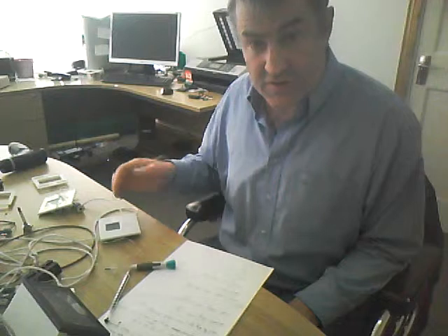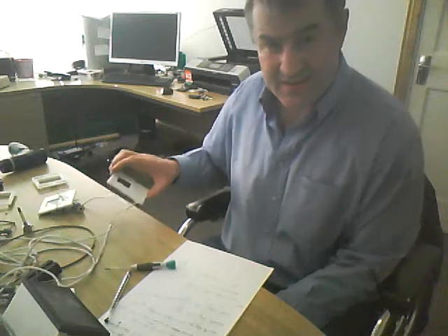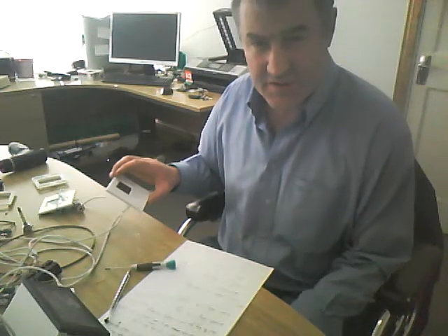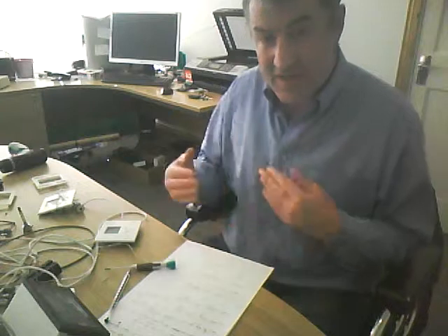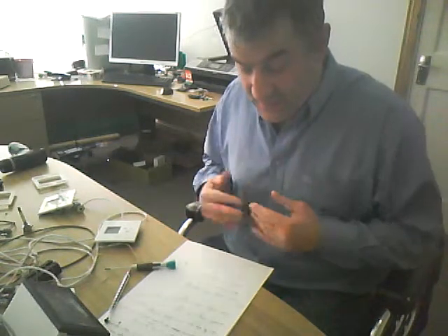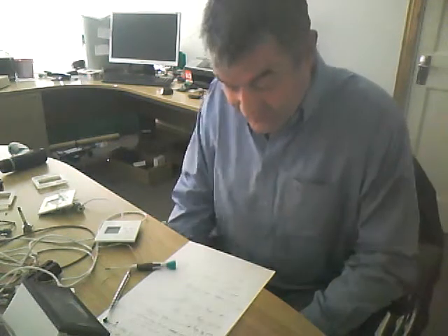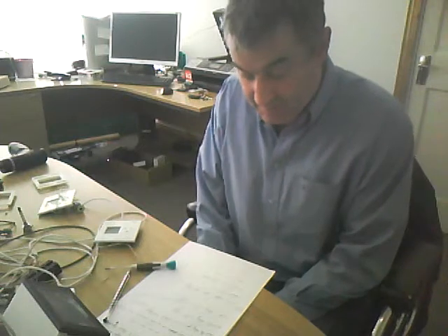So it's differential 5. And it's enabled by the set point of channel 2 in that guy there. That's the guy that normally would measure the water temperature, would be always channel 2. And you set that again to zone 5. So it's SPCH25, and that's enabled on that relay. So now you've set up the relay with your activation and your enable.